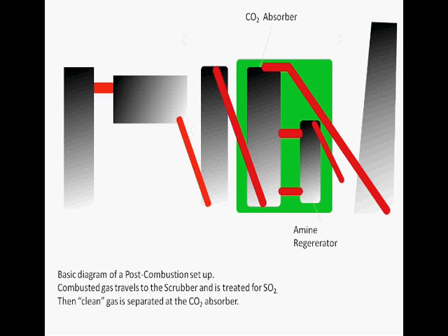And what happens is, after the flue gas is scrubbed for SO2, it goes into the CO2 absorber, where the CO2 gets captured by the amine. It is then scrubbed, regenerated, sent out to compression, and then flue gas goes on out.